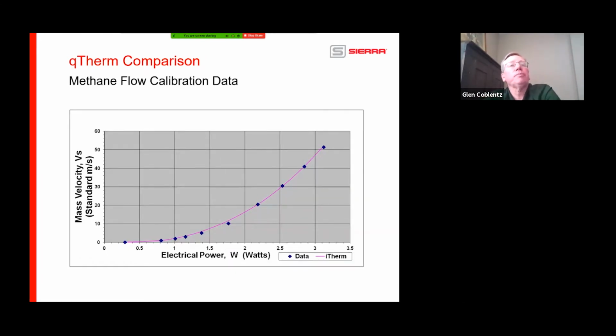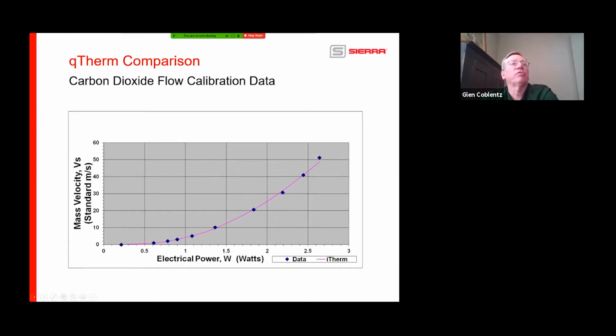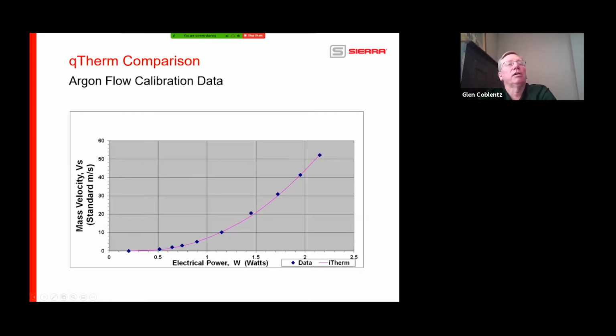Now let's move to methane. Again, the purple line is what the Q-Therm brain thinks the flow rate should be at these various different heat loss conditions. We put it on there and we actually see what the actual data is. It lines up perfectly. Do the same thing for carbon dioxide, a much harder gas to approximate. You can see what the Q-Therm thinks it should be and what the real data is right there. And argon, again, another hard gas to do this with. Again, the Q-Therm brain is right on the money, and you see the data points coming down. So the whole upshot of this is when you're switching gases and using that field flexibility, you're getting some tremendous accuracy in the field.